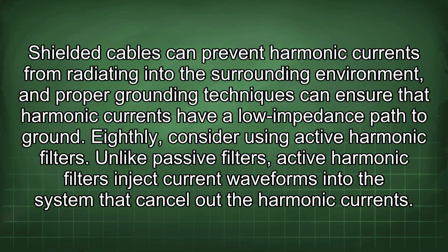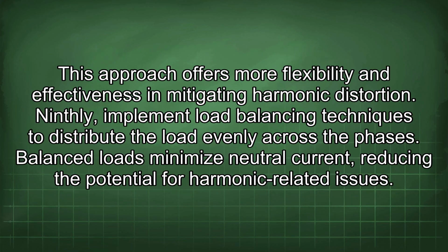Shielded cables can prevent harmonic currents from radiating into the surrounding environment, and proper grounding techniques can ensure that harmonic currents have a low impedance path to ground. Eighthly, consider using active harmonic filters. Unlike passive filters, active harmonic filters inject current waveforms into the system that cancel out the harmonic currents. This approach offers more flexibility and effectiveness in mitigating harmonic distortion.